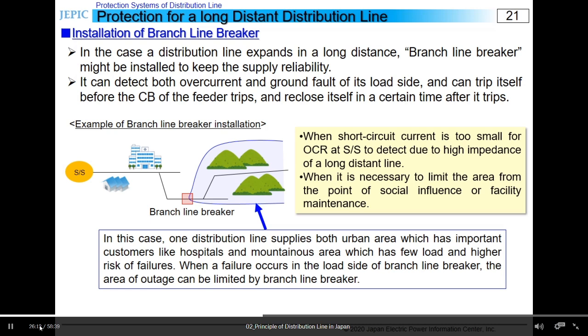When a failure occurs in the load side of it, branch line breaker can localize the outage area and prevent it from expanding to its supply side. As distribution line expands in a long distance, the line impedance also becomes larger. This sometimes makes the short circuit current too small to detect at substation. In this case, a branch line breaker with a function only to detect short circuit current is installed.